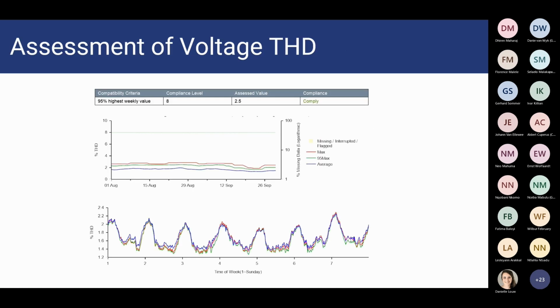So just an example of assessment of voltage THD. In this case, we have a measurement point where we are doing an assessment over a month period. The assessed value, the highest 95th percentile 10-minute voltage THD value in this period, was measured as 2.5%, and compared to 8%, you can see it's complying. It complies to the standard, and this is just a sliding graph that shows you how the voltage THD changes over this month period. The red graph is the maximum value, the green graph is the THD for the 95% of the time value, and then you have your average, which is the blue graph.